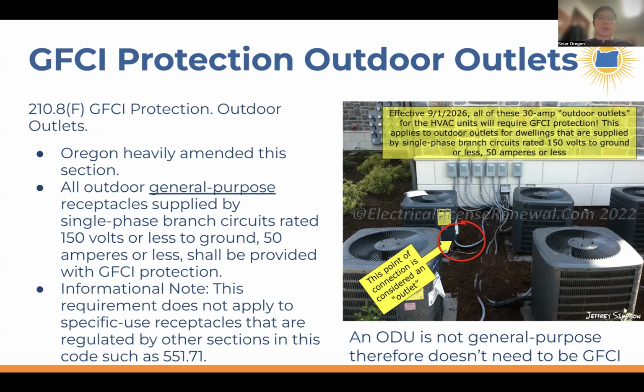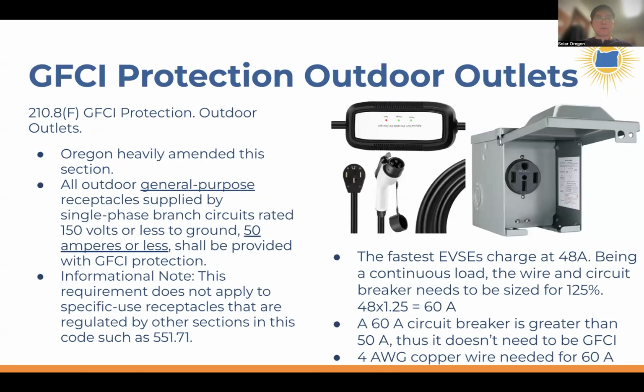Oregon, in their adoption of the 2023 electric code, didn't want to put a specific date because the industry is really unsure what that date will be. So their language for outdoor GFCI protection says general purpose receptacles need GFCI protection, but the outdoor AC/heat pump unit is not general purpose, it's specific, so therefore it doesn't qualify. That's Oregon's solution for dealing with a date that's a constantly moving target.